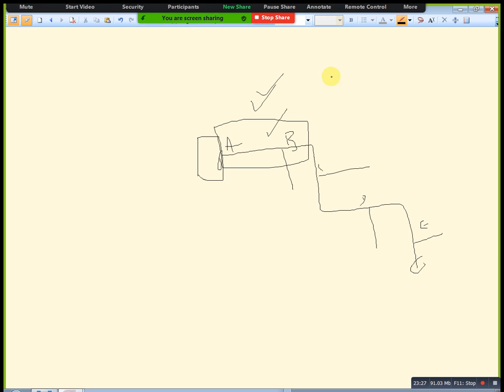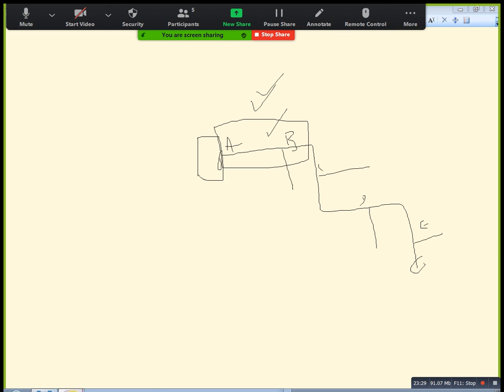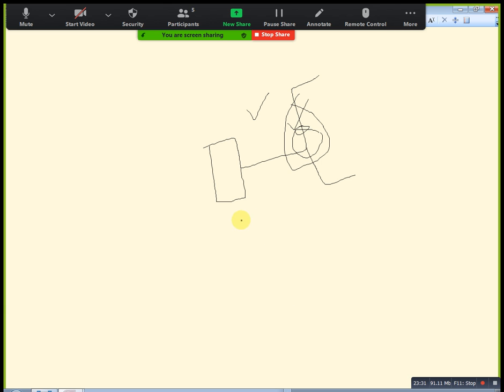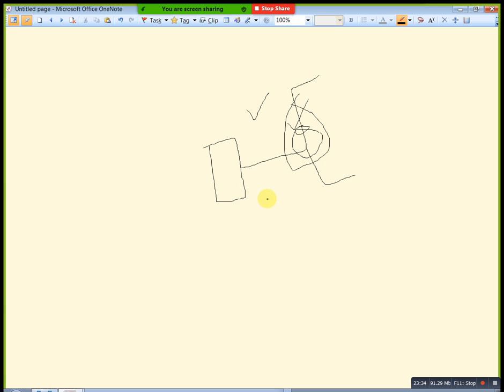See here we have a symmetrical shape; this side we have the same portion, this side we have the same portion. In this type of condition VCDs are not applicable, we don't need VCDs. But when you take a non-symmetrical layout, where only one branch is there, definitely you need to place one VCD, volume control damper.